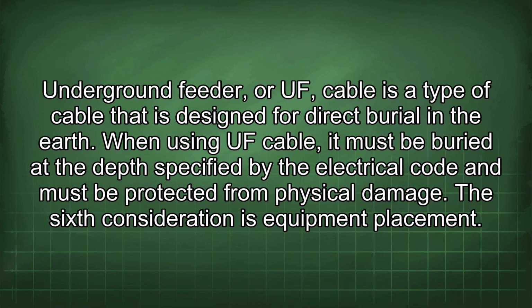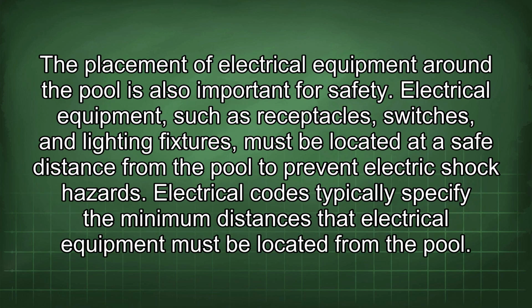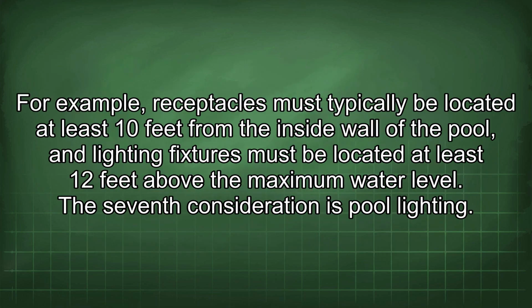The sixth consideration is equipment placement. The placement of electrical equipment around the pool is also important for safety. Electrical equipment, such as receptacles, switches, and lighting fixtures, must be located at a safe distance from the pool to prevent electric shock hazards. Electrical codes typically specify the minimum distances that electrical equipment must be located from the pool. For example, receptacles must typically be located at least 10 feet from the inside wall of the pool, and lighting fixtures must be located at least 12 feet above the maximum water level.